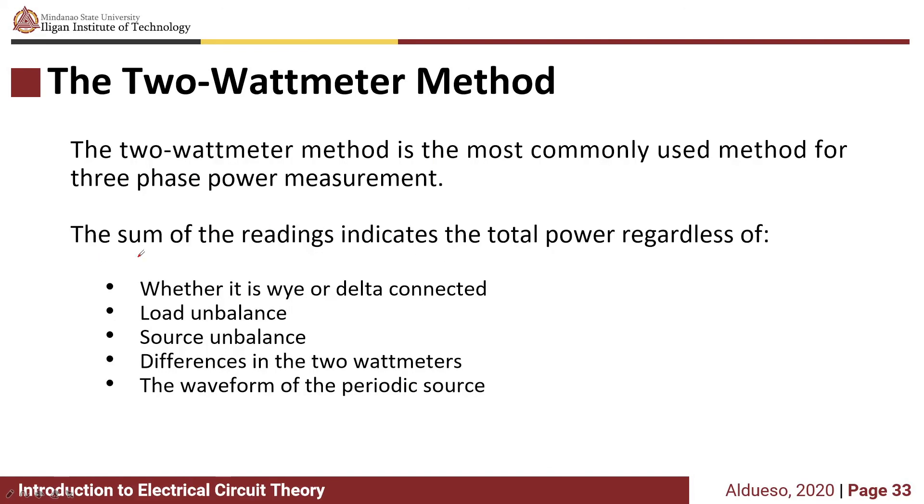The two-wattmeter method indicates the total power regardless of whether it is Y or delta connected, load unbalance, or source unbalance. It is applicable to unbalanced and balanced systems and accounts for differences in the two wattmeters and the waveform of the periodic source.